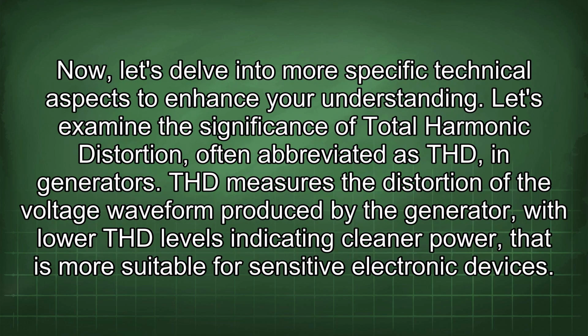Now let's delve into more specific technical aspects to enhance your understanding. Let's examine the significance of total harmonic distortion, often abbreviated as THD, in generators. THD measures the distortion of the voltage waveform produced by the generator, with lower THD levels indicating cleaner power that is more suitable for sensitive electronic devices.